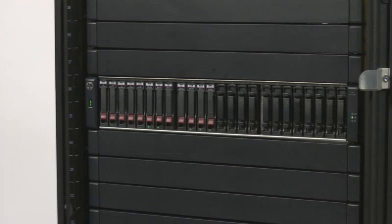In operational systems, if additional hardware components, such as a second controller, need replacing or installing, wait 30 minutes before proceeding with those procedures. This time frame ensures that the controllers and their ownership of V-discs are fully stabilized.